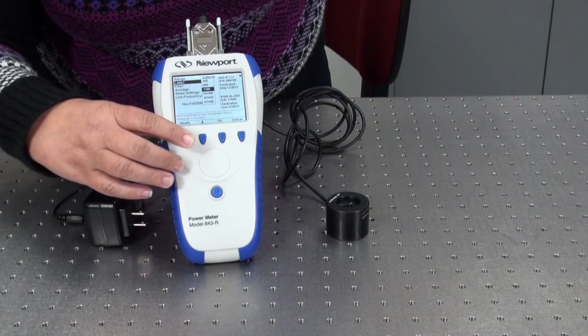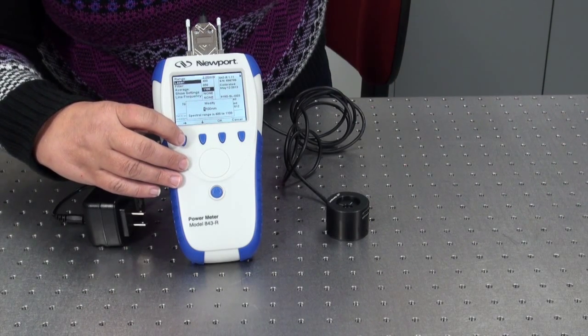The laser menu is used for setting the wavelength of the source that you will be measuring. If the wavelength you require is not listed but is within the calibrated spectral range of the detector, you can select any listed entry for editing by using the down arrow soft key and then the modify soft key.